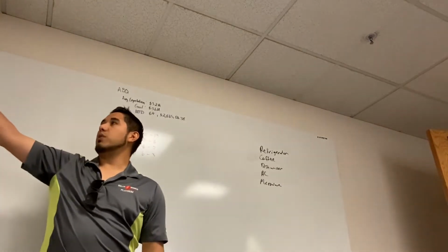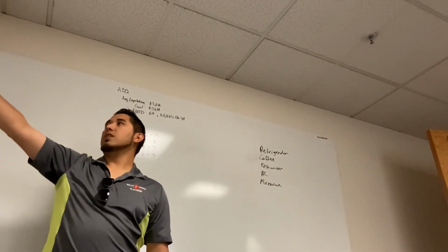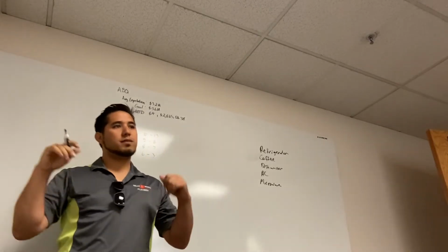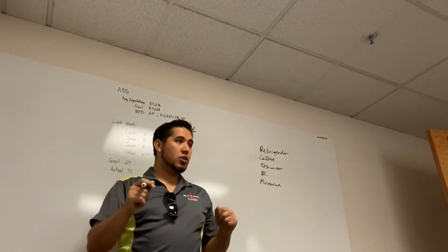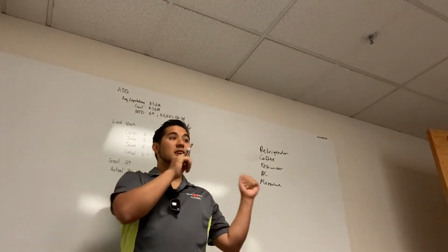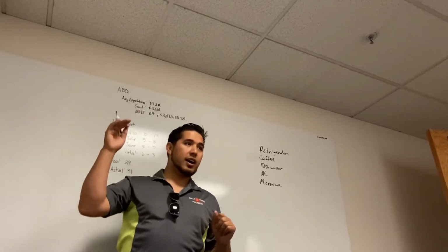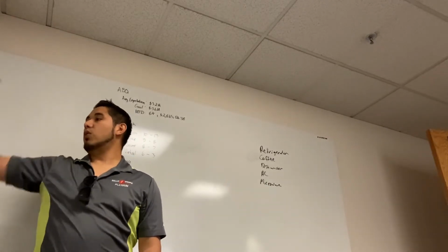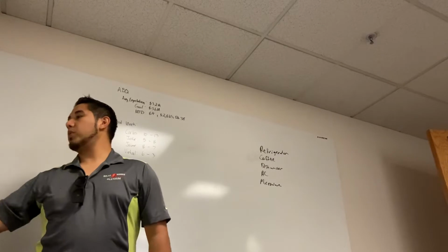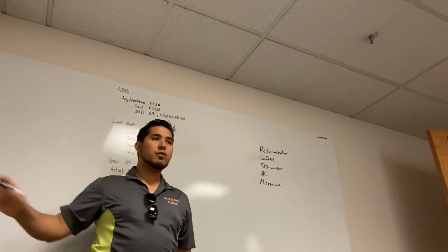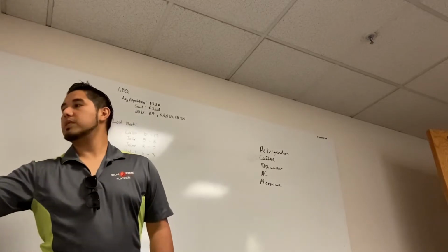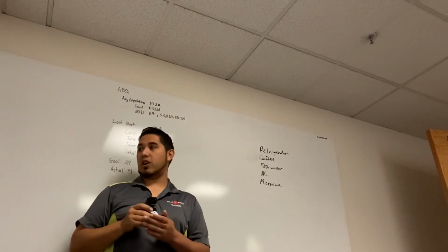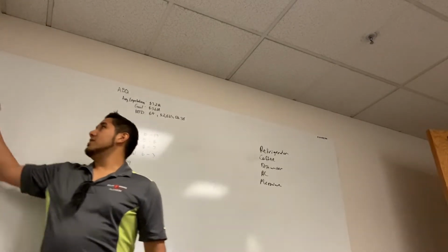So what we do is we would multiply the voltage. Now, sometimes things have a voltage range. So they'll say 110 to 120 or 115 to 120, or they'll just say 115, or they'll just say 120, or sometimes they'll say 220 to 240. Always take the higher. Always take the higher. So what you do is you would multiply, voltage is 120, amperage is 5, 120 times 5 would be 600 watts, which in this case, this tag had the power rating on it already.